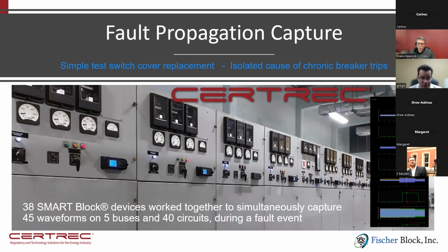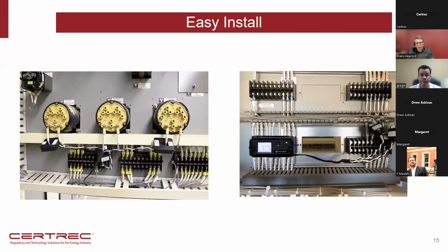So in one day, we installed 40 devices, and then within 10 days, I think they had their first event where we now have provided them a 40 waveform sequence of events capture. And so you just scroll down, all 40 waveforms are on one time axis, and provided them the visibility and the information they needed to do the diagnostic analysis. Now we're providing predictive analytics in these stations as well. So really, part of the example here is the ease of installation. You can actually install them in a day compared to a digital fault recorder of old, where you're not actually having to wire into a digital fault recorder. You're just pulling straight off of the pins.